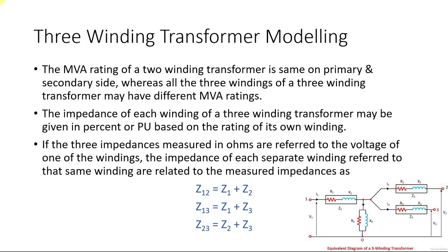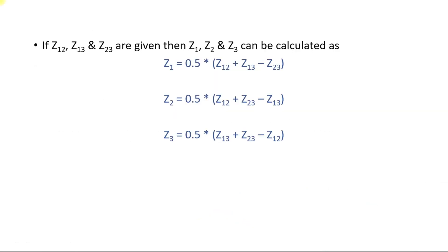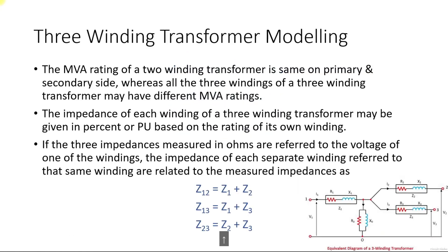Usually you will be given Z1, Z2, and Z3 in per unit on their own MVA ratings. The impedances can be calculated as follows: Z12, from the HV side to LV side, equals Z1 plus Z2. Similarly, Z13 equals Z1 plus Z3, and Z23 equals Z2 plus Z3. So by adding the respective winding impedances you obtain the impedance between any two windings.